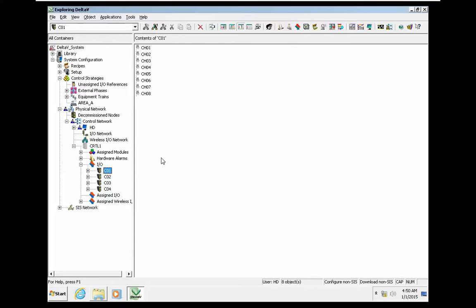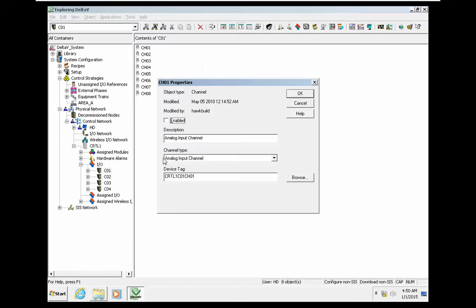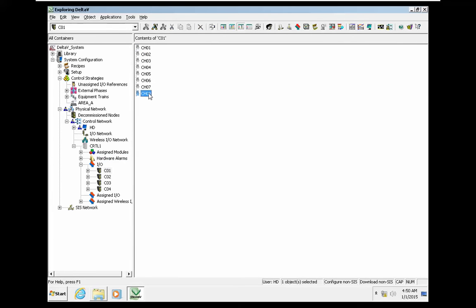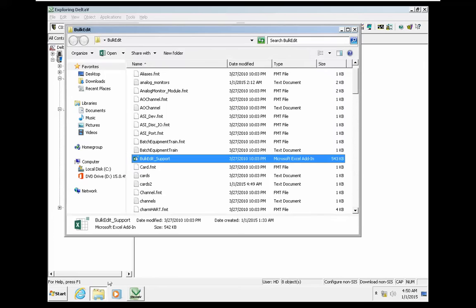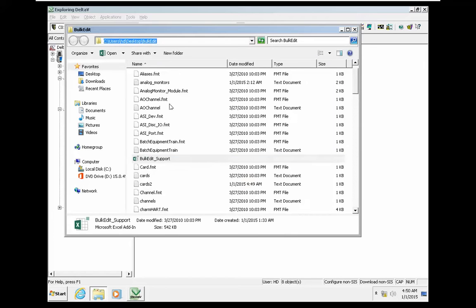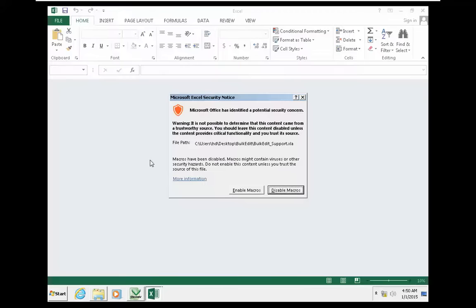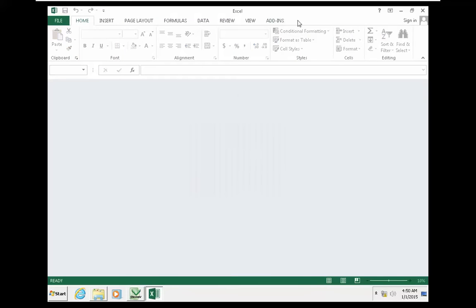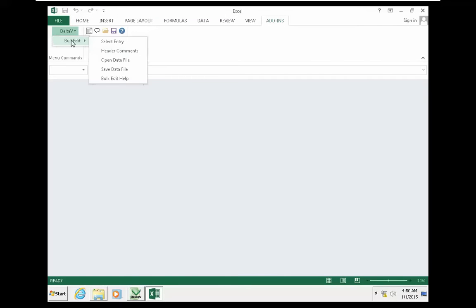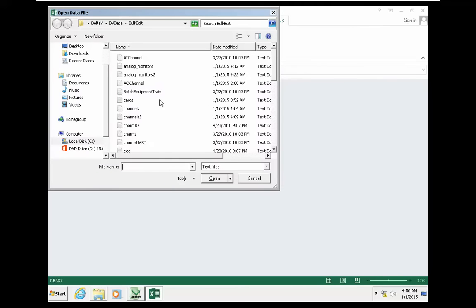We now have four cards on different slot positions in this controller. You can see the controller name, positions, and type of card — the assignment is done automatically. The next step is enabling these modules automatically. It would be very difficult to enable them one by one, so I go to the bulk edit tool again, enable macros, and open the data file related to channels.